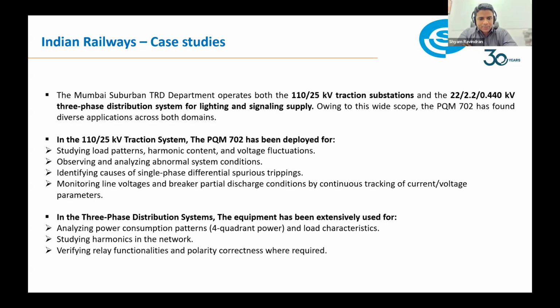So we started monitoring the neutral and phase current in the secondary, which causes the differential tripping. We observed a sudden surge in current, or a drop in current values, in the two different phase and neutral. This caused the differential relay to trip. Then we started identifying the basic source, and when we checked the whole control wiring, we identified that the wiring had a small issue where the current had a leakage, and this caused the spurious tripping. So this is from the point of view of differential tripping.